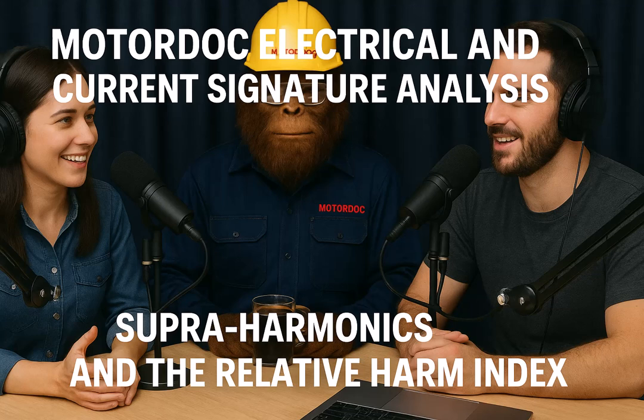Sure. There was a DFIG wind turbine tower bearing example. It showed an RHI of around 3 at 5 kilohertz. RHI of 3, so 1,000 times the harm. Roughly, yeah. According to the scale, that's very high potential harm. Immediate attention needed. And apparently that turbine did have a history of bearing discharge issues. Okay, that makes sense. Any other examples? Another one involved a fan. The ground current showed an RHI over 2, up around 20 kilohertz. RHI over 2, so 100 times harm at 20 kilohertz. Right. Now, the actual current level might not have looked that scary on its own, but the high RHI at that high frequency pointed to a significant risk of eventual bearing failure from electrical discharge.